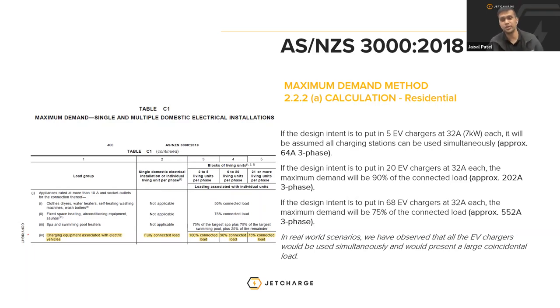And if the design intent was to put, suppose, 68 EV chargers, you would split the number of chargers evenly across the 3 phases and then multiply it by 32 and then have 75% of the connected load, so approximately 552 amps, 3-phase. In real world scenarios, we find that these values can be a bit different because typically residents plug in their EV chargers at exactly the same time and provide what's called a large coincidental load. So the diversification figures used in AS3000 may not necessarily be the best indication of what the building actually uses from day to day. Next slide.